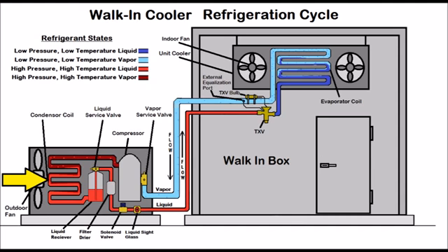So then it continues to reject heat until it turns into a complete liquid. Then the liquid refrigerant lowers in temperature as it rejects heat and turns into a subcooled liquid. The subcooled liquid is the temperature difference between where it comes out of the saturated state as a complete liquid until where it comes into the liquid receiver. Subcooling is the temperature decrease in liquid form.